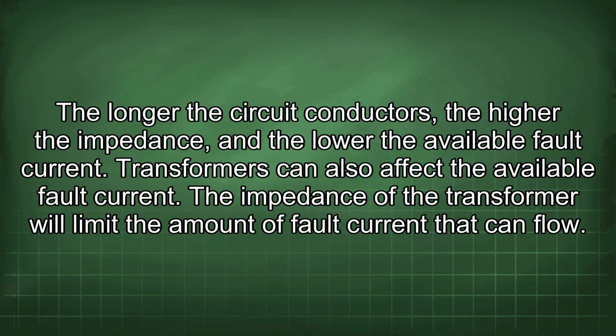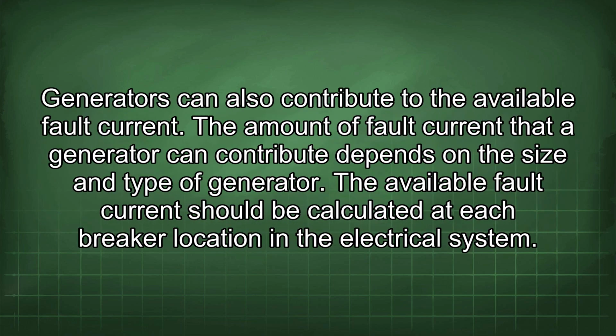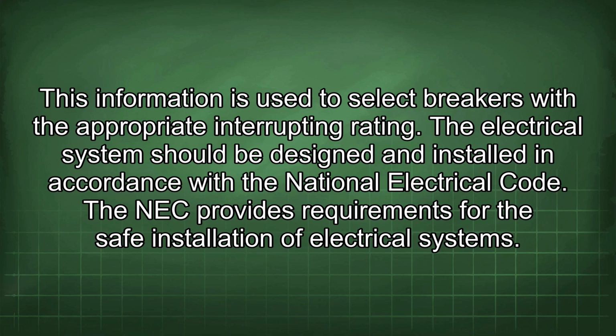Transformers can also affect the available fault current. The impedance of the transformer will limit the amount of fault current that can flow. Generators can also contribute to the available fault current. The amount of fault current that a generator can contribute depends on the size and type of generator. The available fault current should be calculated at each breaker location in the electrical system. This information is used to select breakers with the appropriate interrupting rating.